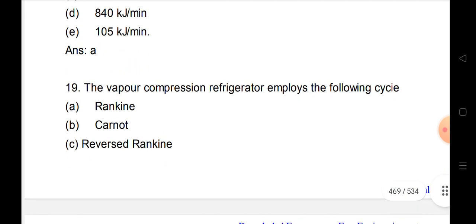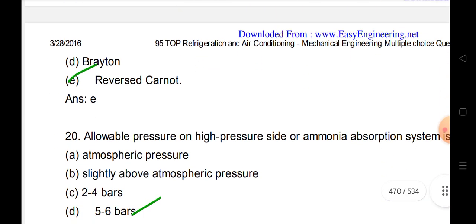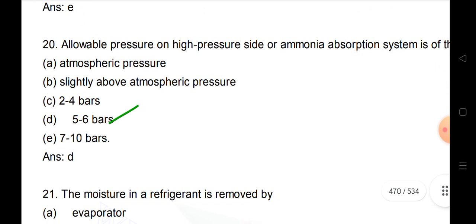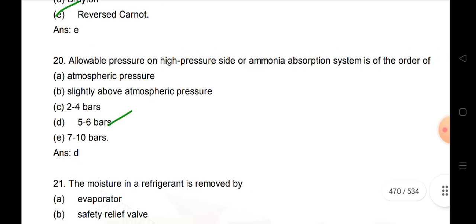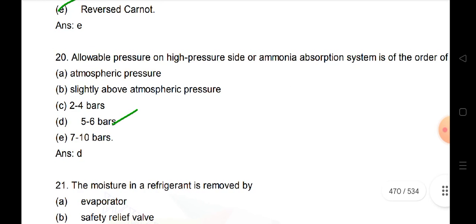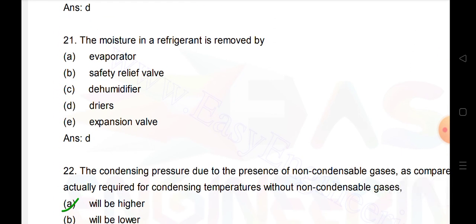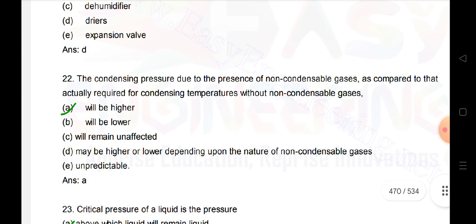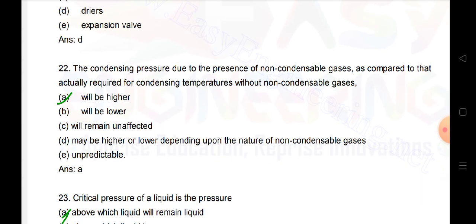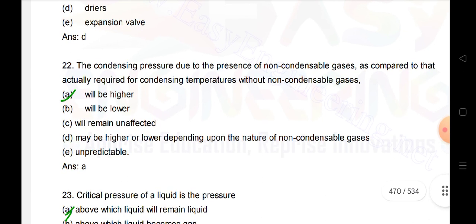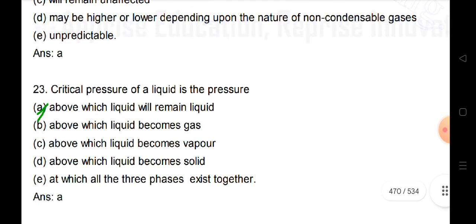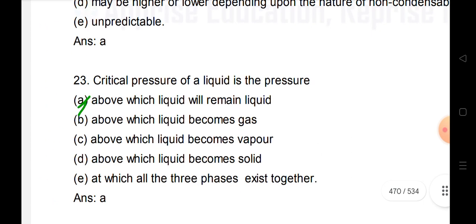The vapor compression refrigerator operates on the reverse Carnot cycle. In the ammonia absorption system, pressure on the high pressure side is of the order of 5 to 6 bars. The moisture in a refrigerant is removed by dryers. The condensing pressure due to the presence of non-condensable gases as compared to the actual required for condensing temperature without non-condensable gases will be higher.